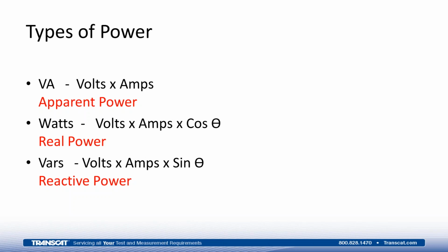As soon as we apply a reactive, phase-oriented load, a load that does not have the voltage and current being drawn at the same time, these devices would cause a difference in the measurement capabilities. And in order to measure the actual wattage, which is the expression of energy, we would have to measure volts times amps. We would have to measure the phase angle, sometimes called the power factor, between the voltage and current, and that would go into the calculation.